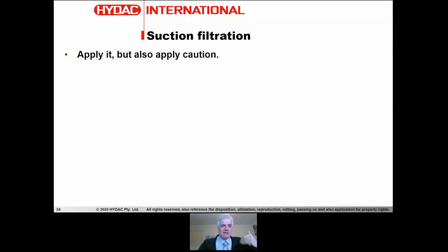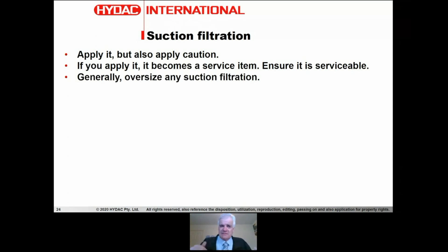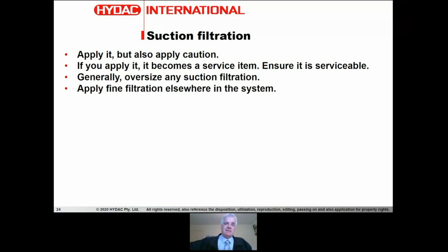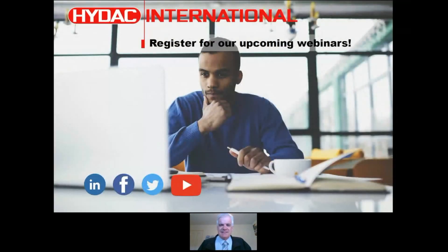In summary: suction filtration can be applied but with caution, as it is problematic for many applications. If you do apply it, make it accessible as a service item. For fine filtration in the suction line, oversize it and avoid cavitation at all costs. Fine filtration can be applied elsewhere in the system. Suction filtration protects the pump, but it's not the only filtration in the system and is typically very coarse, so you won't achieve the fine cleanliness levels desired in oil systems.